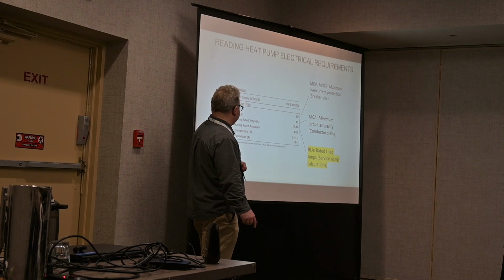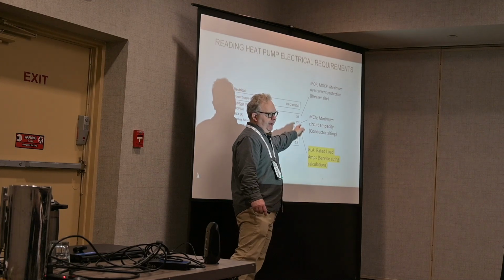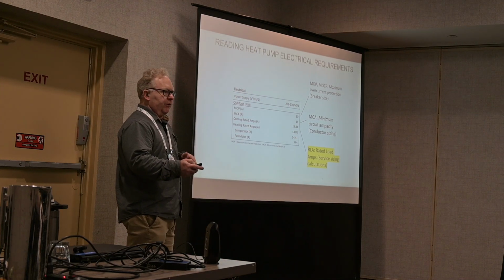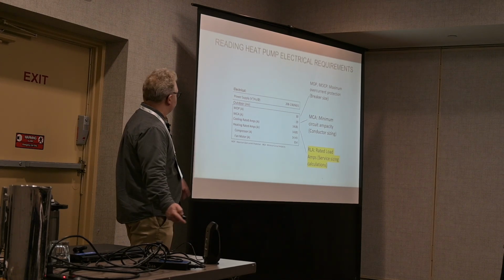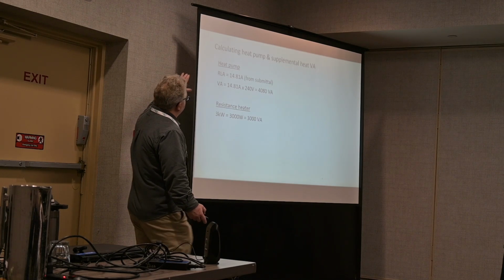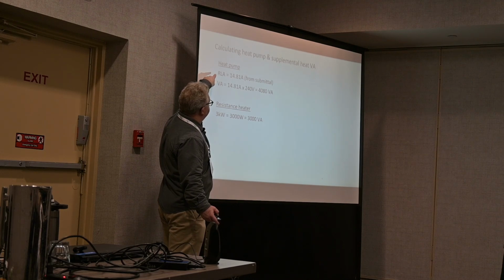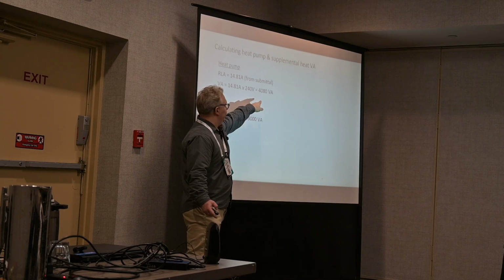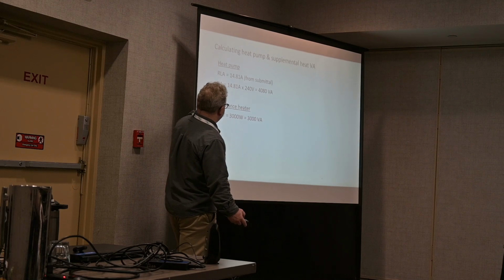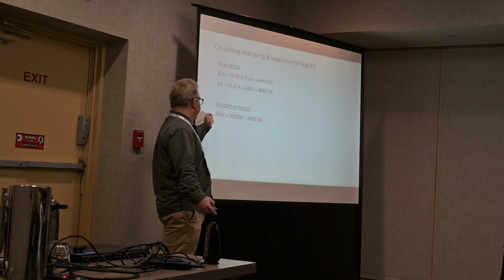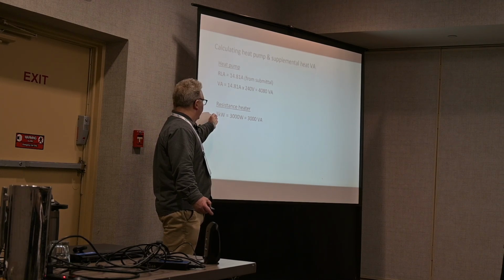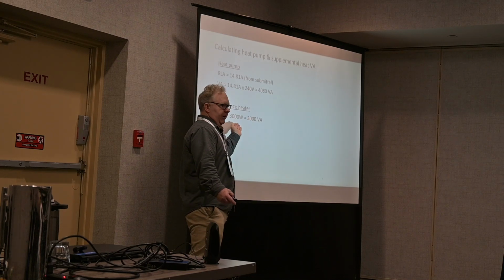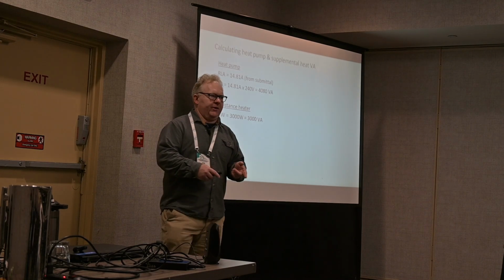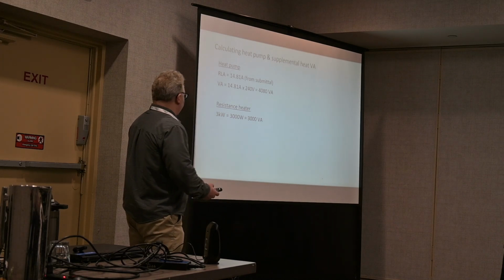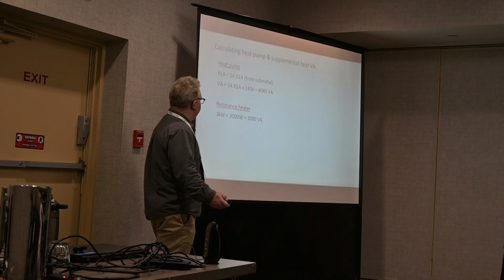Now, in the case of this system, it's 14.81 amps in both heating and cooling. You may get some systems that have different ratings in heating and cooling mode. And again, you're going to be choosing the larger of those two. So to take those rated load amps and convert them into VA, we just take that from the submittal, multiply it by our voltage, and we get our volt amperes. If we want to put in a resistance heater, in this case I'm not, but if we do, its VA for these calculations is just going to be equal to its watts. So our resistance heat kits for our heat pumps are typically rated at 3, 5, 8, 10 kilowatts. That just translates directly into VA.